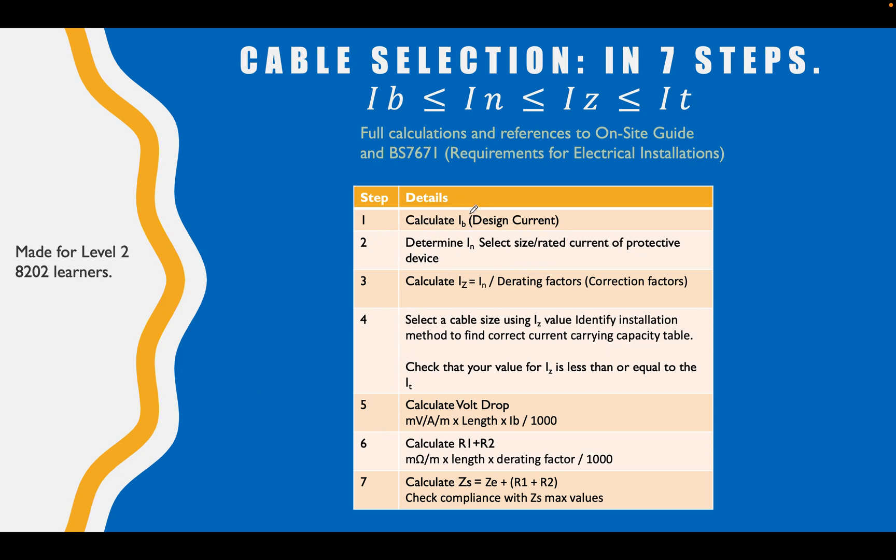Let's run through it now. We're going to go through one to seven: calculate the design current, determine the rated current of our protective device, calculate the Iz which is the current carrying capacity of the cable in the installed conditions, look at correction factors, select a cable using that value we get for our Iz, identify installation methods and go through current capacity tables, calculate volt drop, R1+R2 and Zs. We're going to do full calculations and references to on-site guide and the requirements for electrical installations, the big brown book.